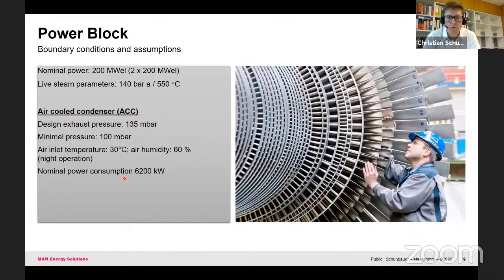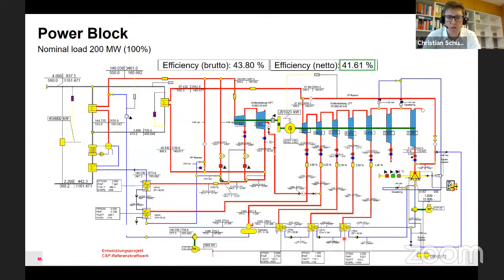In that case, the own consumption of the ACC is 6.2 megawatts. To ensure the minimum temperature in operation, which was mentioned at 245 degrees C, also during load changes - so in part load, this temperature in general would change - we have a bypass where we can preheat this water.